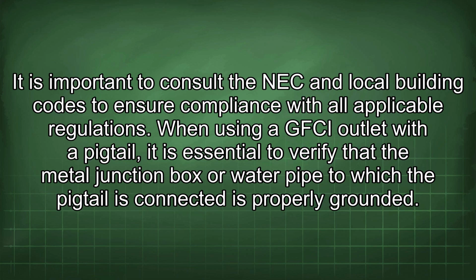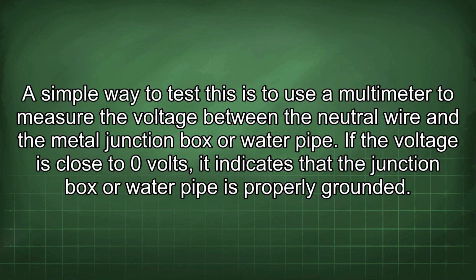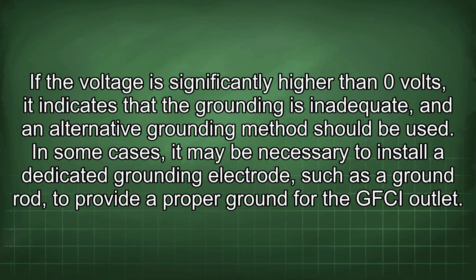When using a GFCI outlet with a pigtail, it is essential to verify that the metal junction box or water pipe to which the pigtail is connected is properly grounded. A simple way to test this is to use a multimeter to measure the voltage between the neutral wire and the metal junction box or water pipe. If the voltage is close to 0 volts, it indicates that the junction box or water pipe is properly grounded.